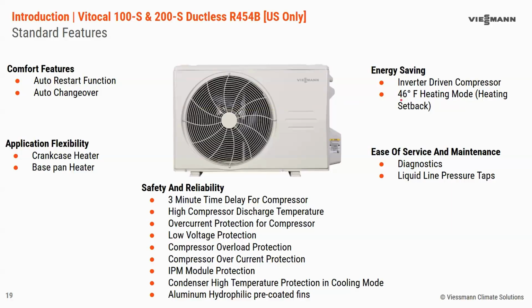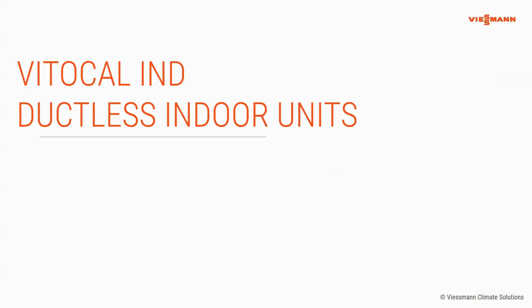The energy savings, of course, you can provide with the inverter-driven compressor. Largely, that's where a lot of the benefits are coming from. There is a heating setback mode built in for applications where you want to keep temperature above freezing, but without actually heating the space and using excess energy for that. And the units also, of course, come with built-in diagnostics and the liquid line pressure taps for if you need to do any work on the refrigerant system.